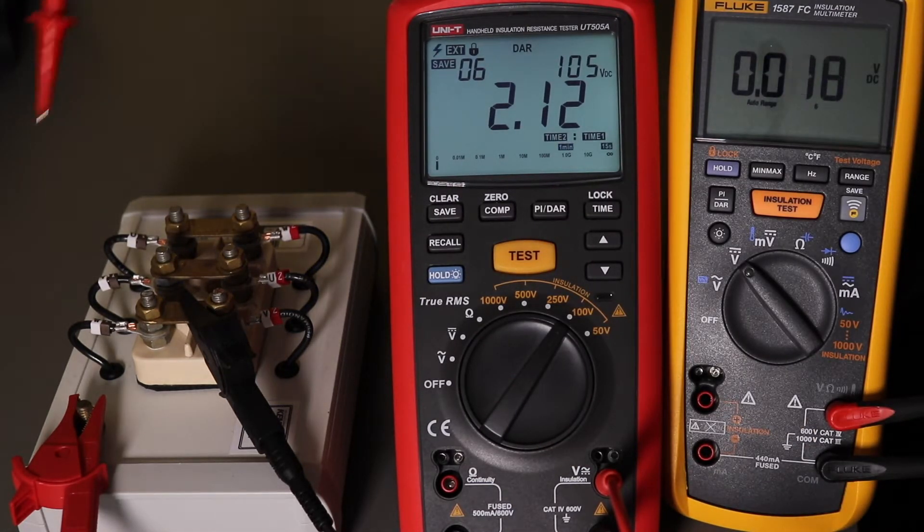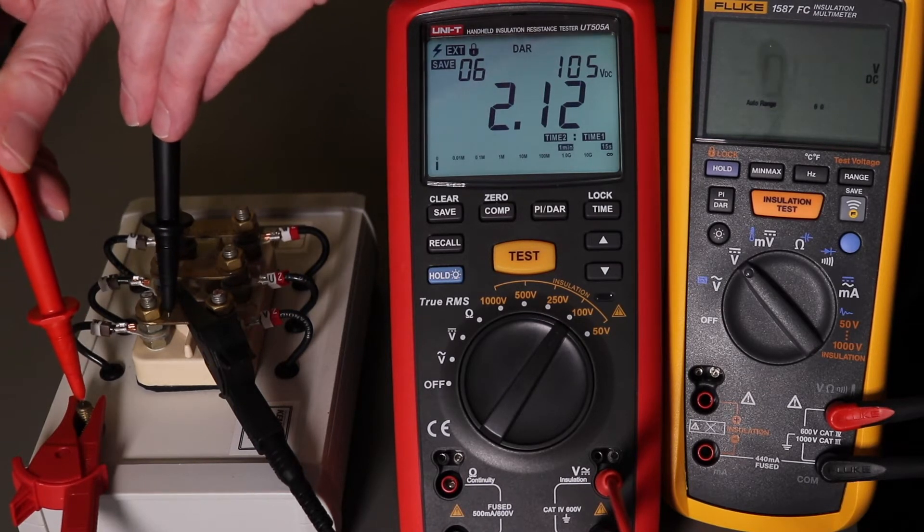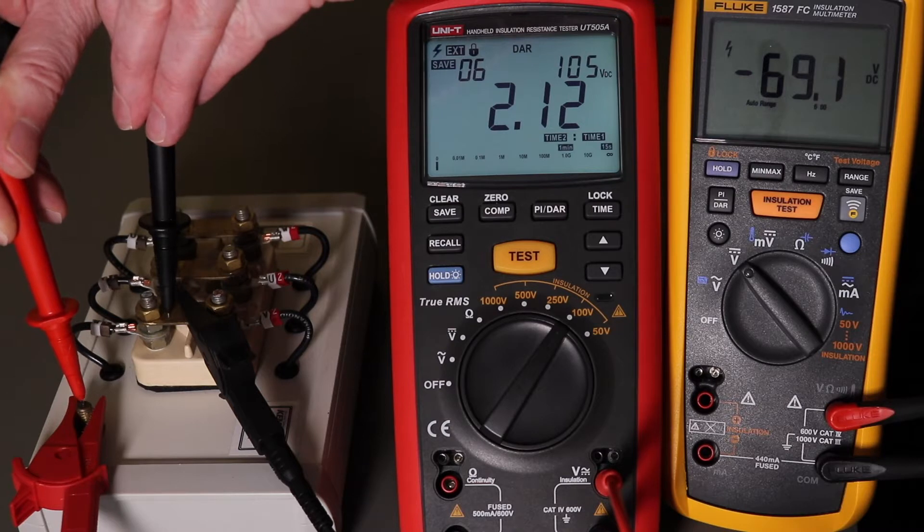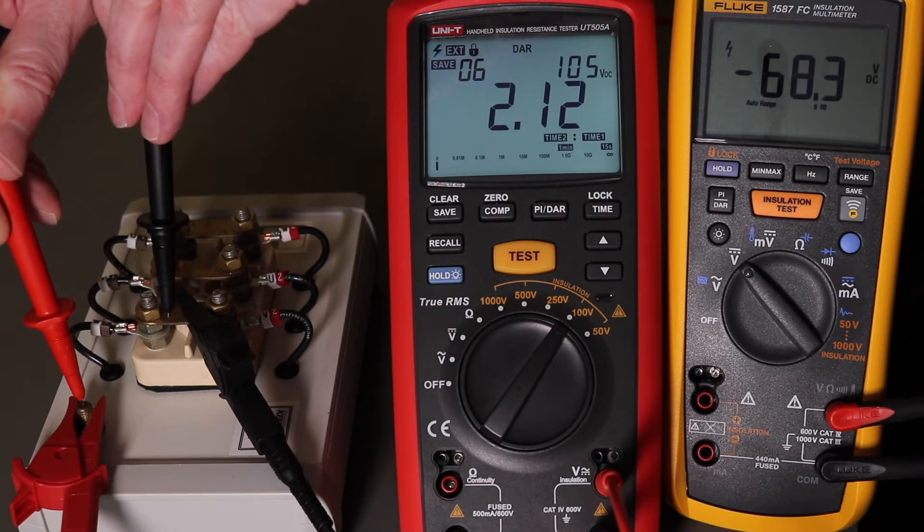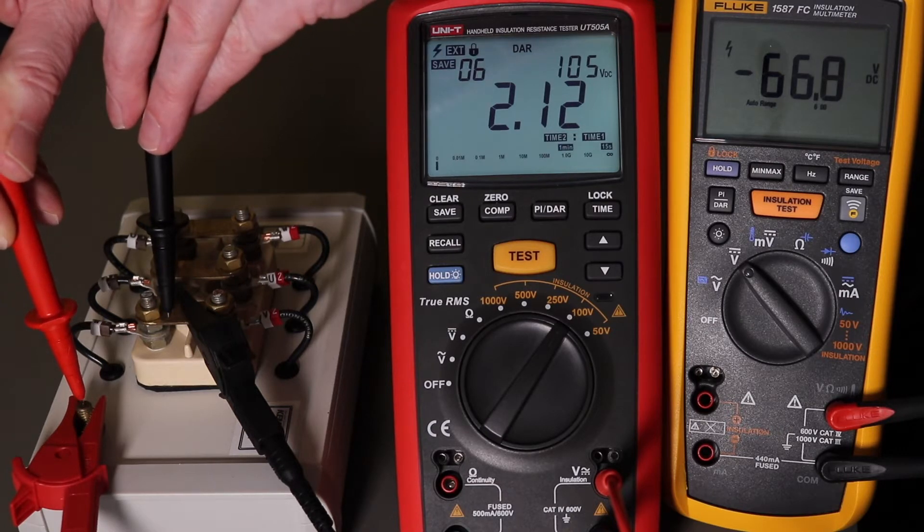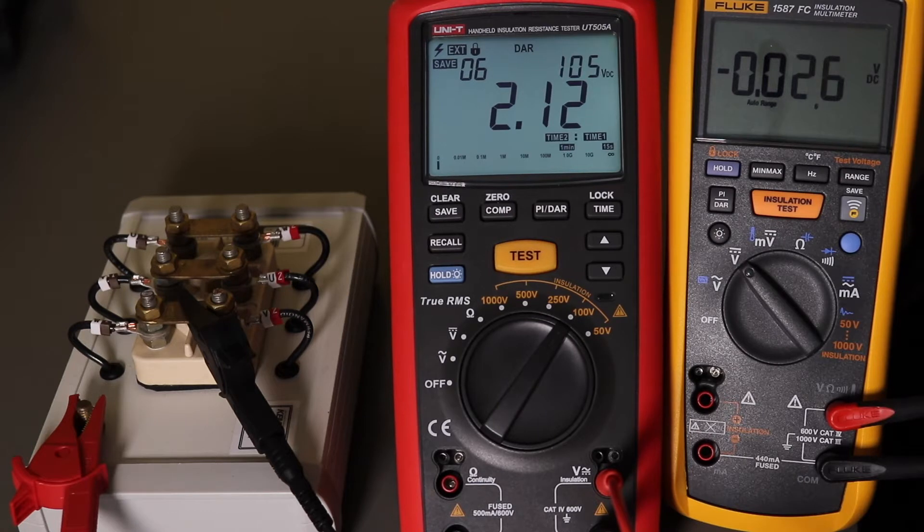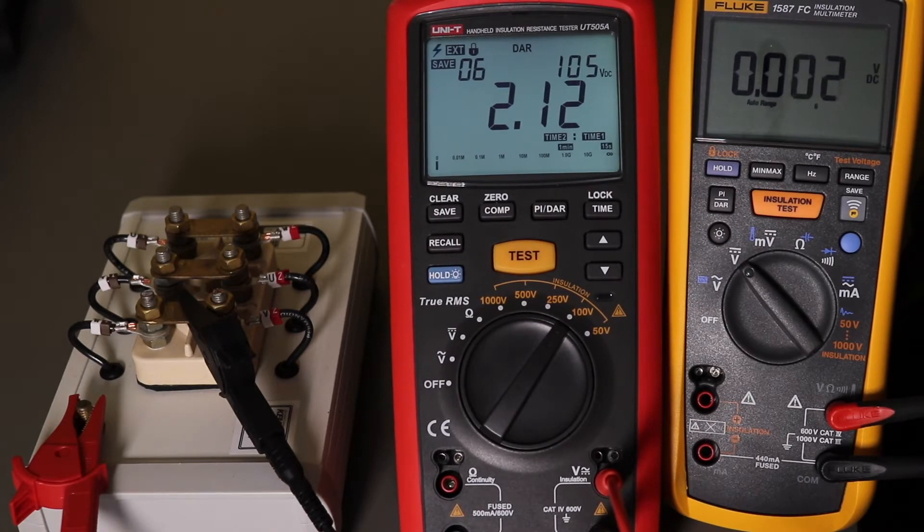Stop the test and put meter on again. You can see the voltage dropping down now, and it takes quite a while for this one to drop because the discharge resistance in this unit is quite high - that's about eight megaohms if I remember.